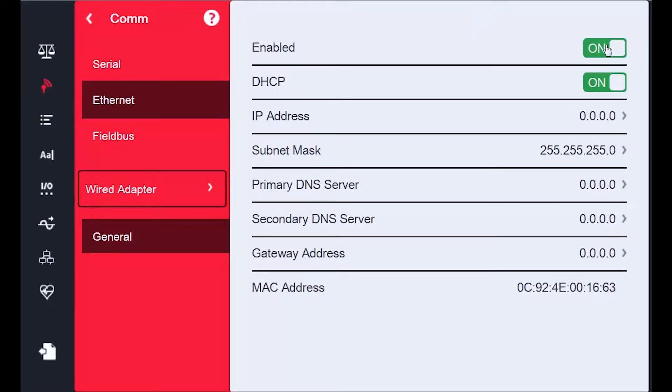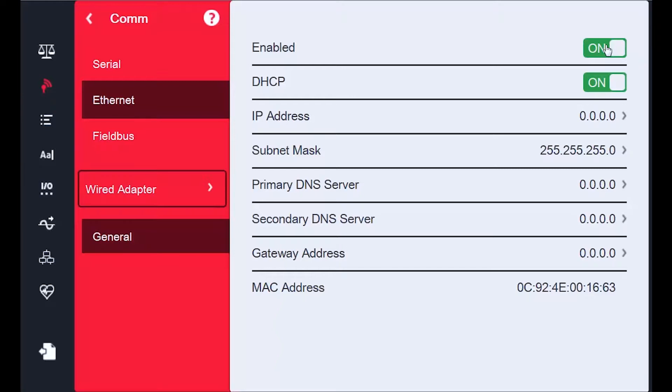In order to obtain an IP address automatically, I will leave DHCP set to On. When installing a 1280 at a customer's site, make sure to find out if they want the 1280 to have a statically set address or not, because if they want to designate an IP number for the 1280, you will have to set DHCP to Off and set the address yourself.